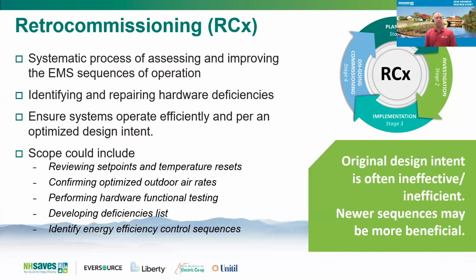One thing that's important is never let energy sacrifice operations and maintenance, because if you do, it'll just get overridden. There should be a marriage between implementing sequences that save energy, but also make sense operationally. If you've got old equipment, you can't necessarily go in and put all these fancy sequences on that old equipment because you might be putting lipstick on a pig. And when that happens, things get overridden and it gives retrocommissioning and controls improvements a bad rap. So you really want to think about the performance of the systems, the existing conditions, and understand what works in the building and what doesn't.